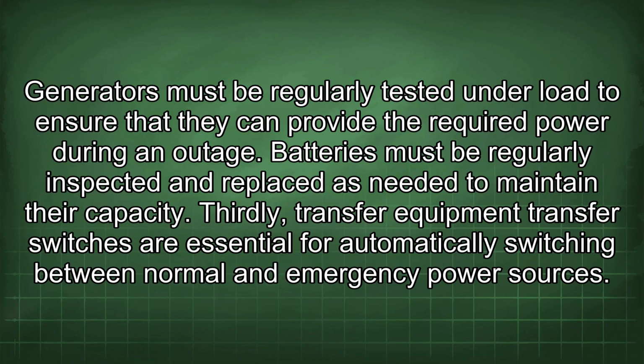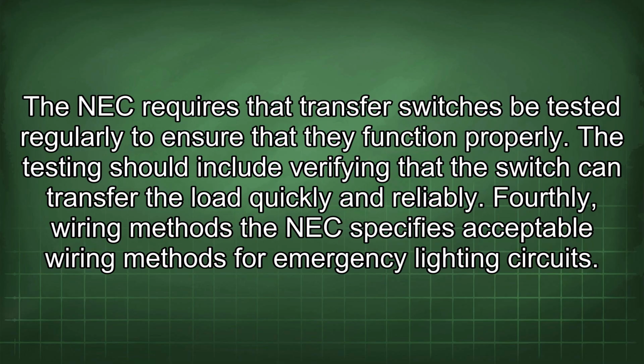Thirdly, transfer equipment. Transfer switches are essential for automatically switching between normal and emergency power sources. The NEC requires that transfer switches be tested regularly to ensure that they function properly. The testing should include verifying that the switch can transfer the load quickly and reliably.